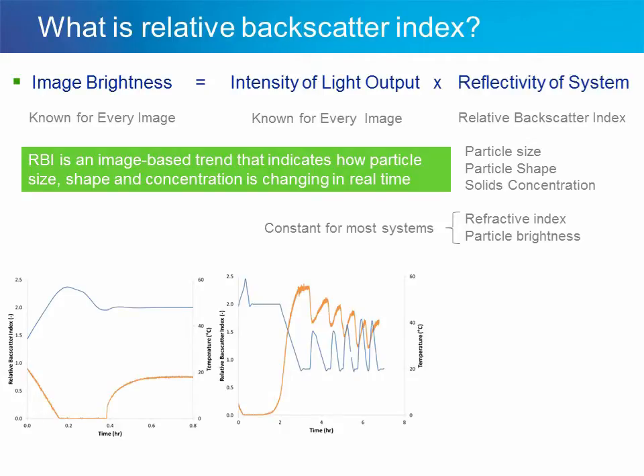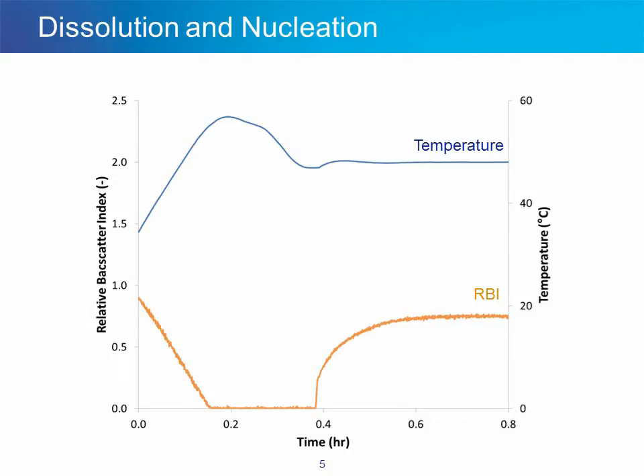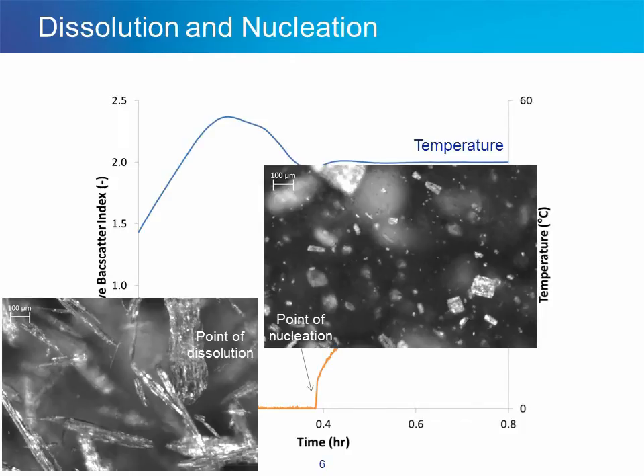Here we have some examples we will go into more detail on. In the first example, we follow a crystallization process where temperature is increased and RBI decreases over time, indicating dissolution of the crystals. As the temperature is reduced, the crystals nucleate. We have the point of dissolution measured by RBI as well as the point of nucleation measured by RBI. Combined with the RBI trend, we have images showing that the size, shape, and structure of the crystals differs at the point of dissolution compared to the point of nucleation.